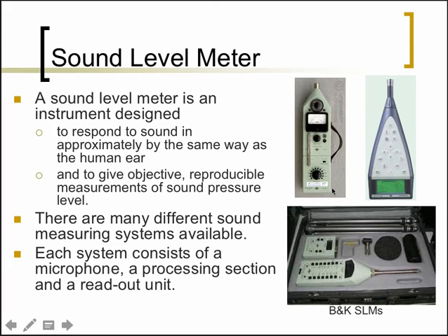So essentially, any of the sound level meter systems will have three components in it. It would have a microphone, of course, to measure the sound, environmental sound, or the sound from the transducer. Then it needs a processing station to convert, for instance, the sound pressure level into its decibel equivalent, or in some cases even do filtering and selectively weigh different filter outputs. And then it needs a readout unit, which can be a digital display, or a needle display over here in those older analog sound level meters.